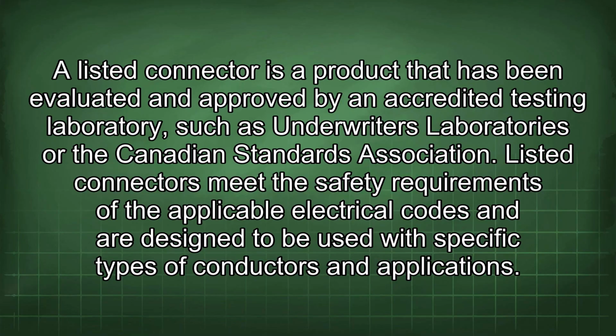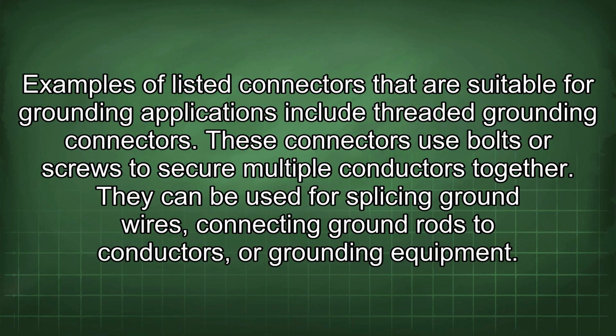A listed connector is a product that has been evaluated and approved by an accredited testing laboratory such as Underwriters Laboratories or the Canadian Standards Association. Listed connectors meet the safety requirements of the applicable electrical codes and are designed to be used with specific types of conductors and applications. Examples of listed connectors that are suitable for grounding applications include threaded grounding connectors. These connectors use bolts or screws to secure multiple conductors together. They can be used for splicing ground wires, connecting ground rods to conductors, or grounding equipment.